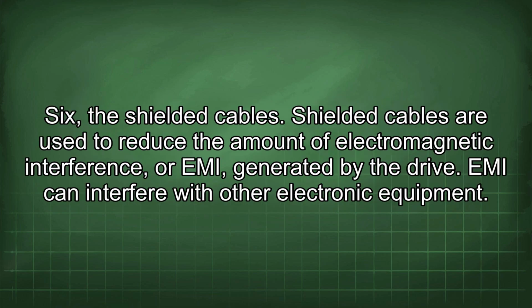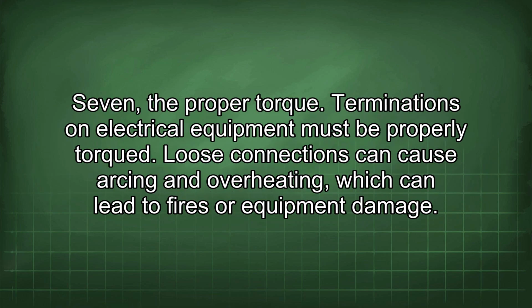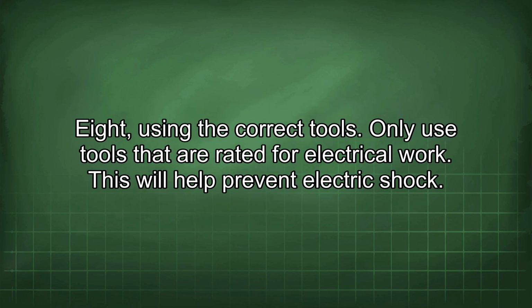Six: the shielded cables. Shielded cables are used to reduce the amount of electromagnetic interference, or EMI, generated by the drive. EMI can interfere with other electronic equipment. Seven: the proper torque. Terminations on electrical equipment must be properly torqued. Loose connections can cause arcing and overheating, which can lead to fires or equipment damage. Eight: using the correct tools. Only use tools that are rated for electrical work. This will help prevent electric shock.